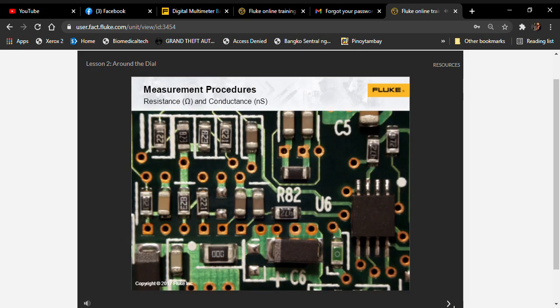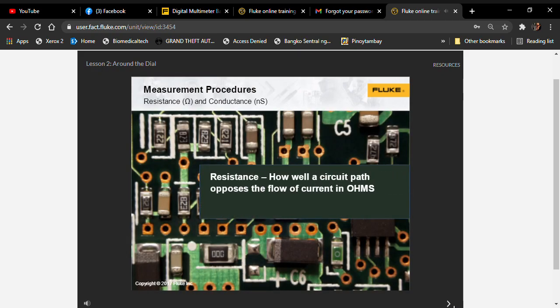A resistance measurement, the next position on the rotary function selector switch, shows how well a circuit path opposes current flow. It's measured in ohms. Conductance is the exact opposite. It's a measurement of how well a circuit path allows current flow, 1 over the resistance value. It's measured in Siemens, or actually tiny fractions of a Siemens called nanosiemens.